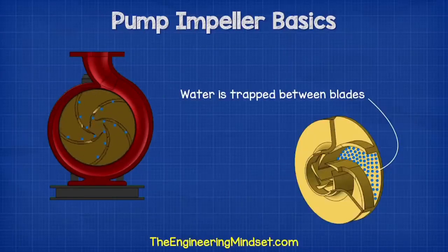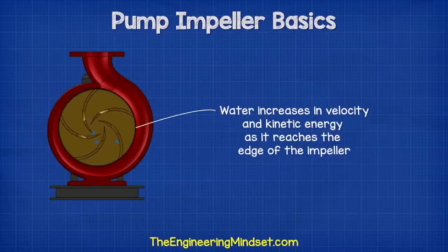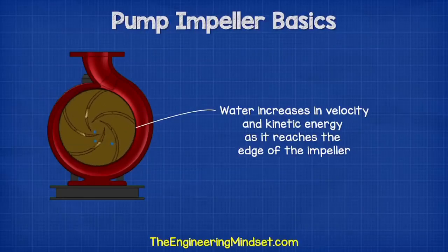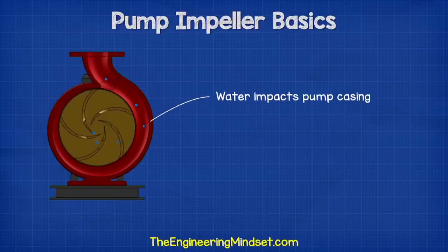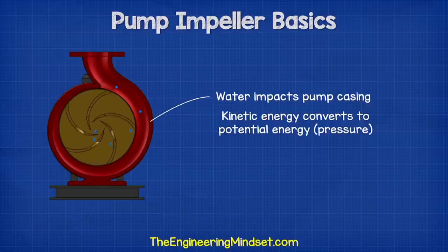The water enters into the eye of the impeller and is trapped there between the blades. As the impeller rotates, it imparts kinetic energy or velocity onto the water. By the time the water reaches the edge of the impeller, it has reached a very high velocity. This high-speed water flows off the impeller and into the volute, where it hits the wall of the pump casing. This impact converts the velocity into potential energy or pressure.